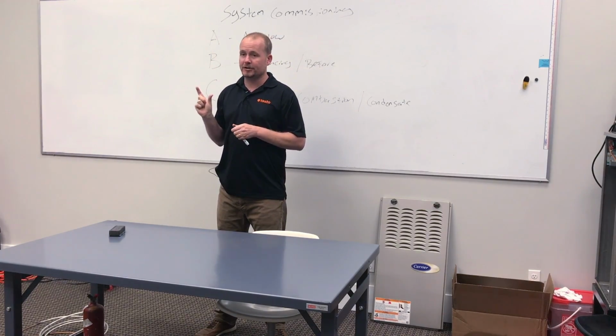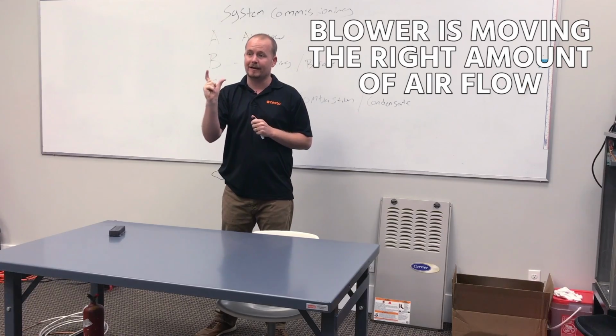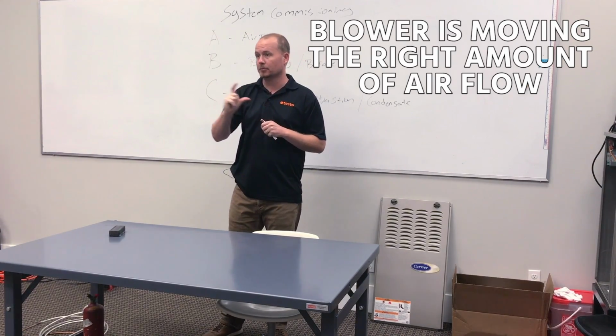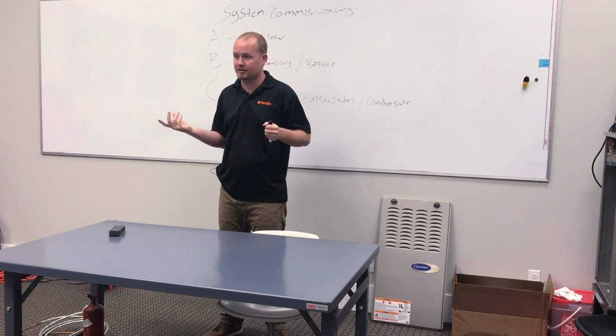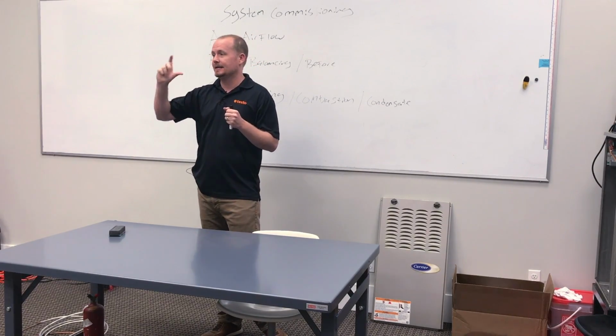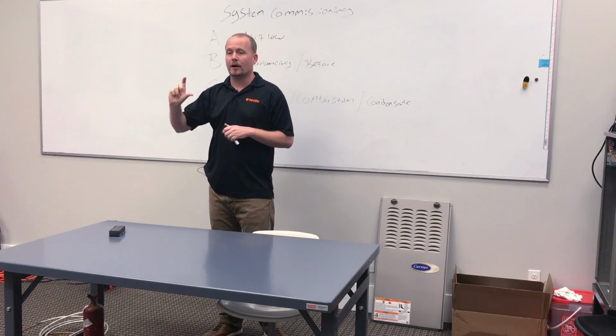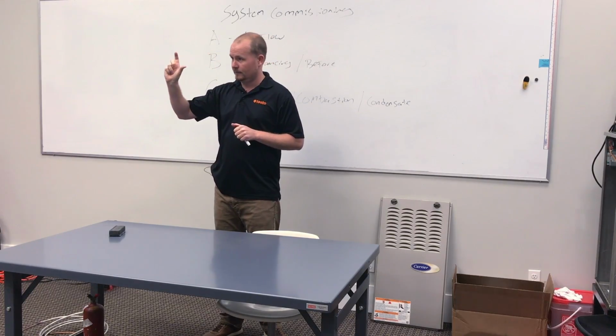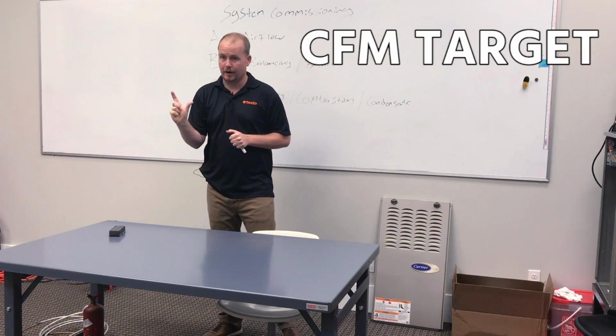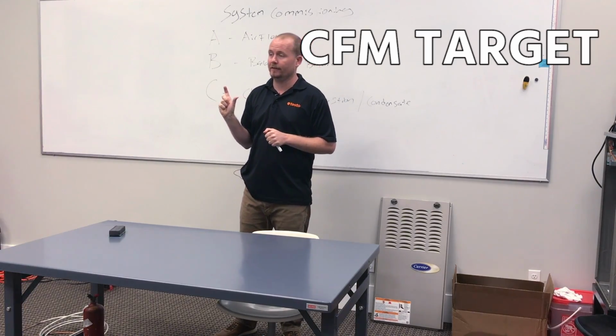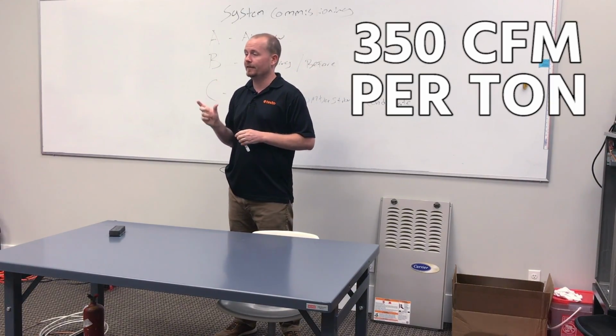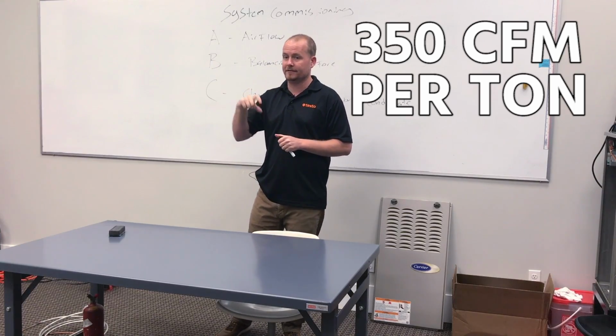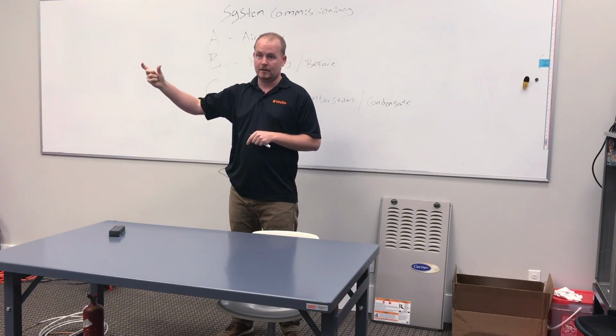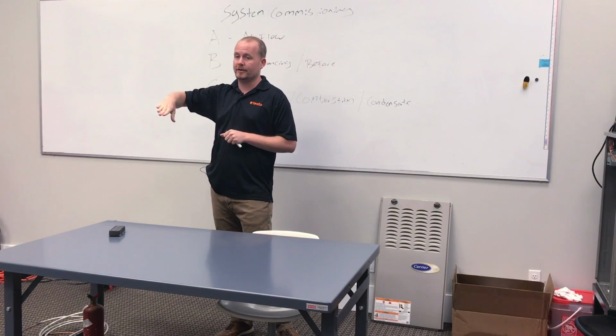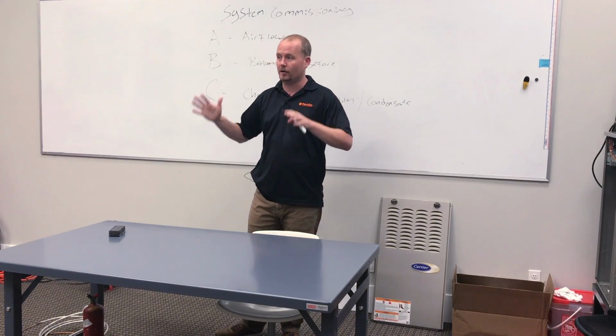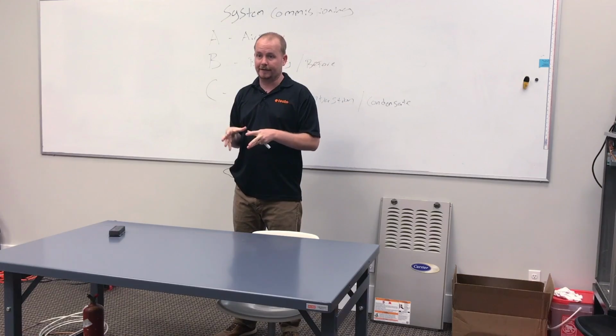And one of the primary assumptions that we're making is that the blower is moving the amount of airflow that it's supposed to move, or that the blower is at least spinning up to the RPM that it's supposed to spin to. And that the blower is the right size, all that sort of stuff, right? So, in order for us to trust static pressure, we should have some idea of our CFM target, right? In Florida, how many CFM per ton are we looking for? 350. 350 CFM per ton is what we're looking for in our market because of the high latent loads, high humidity loads. We run slightly lower airflows than the rest of the country because it pulls more moisture out of the air, colder evaporator coil. That's what we're looking to accomplish, 350 CFM per ton.